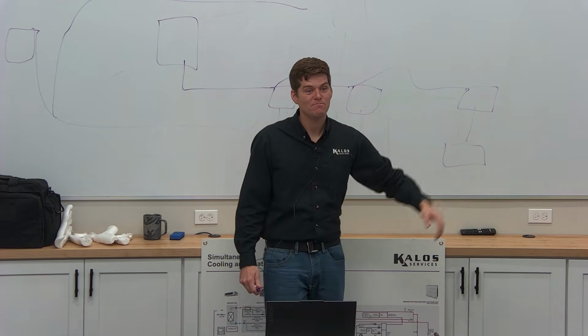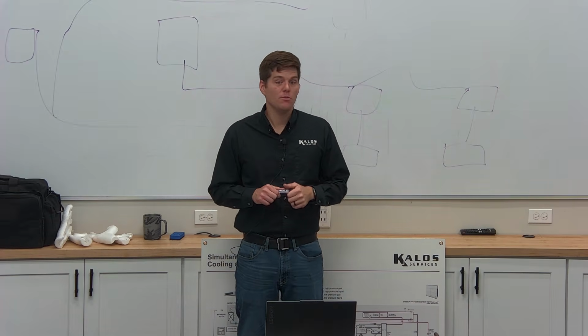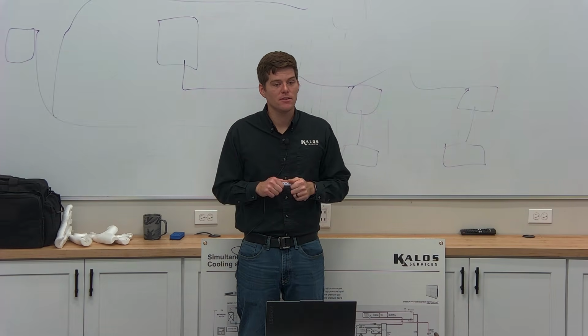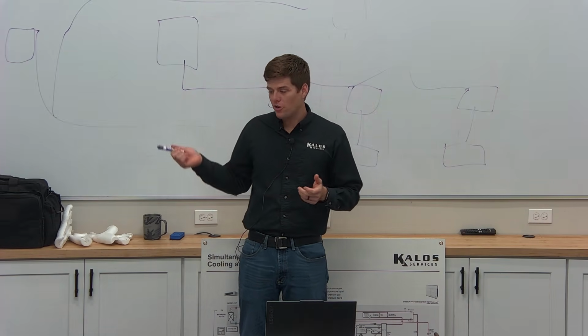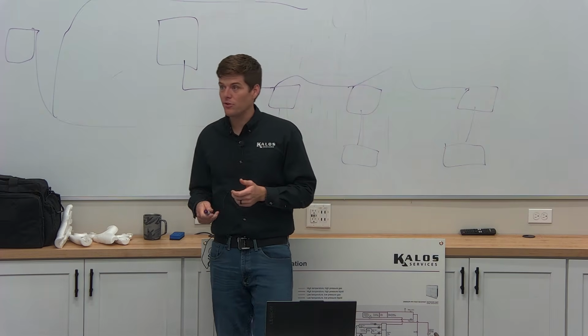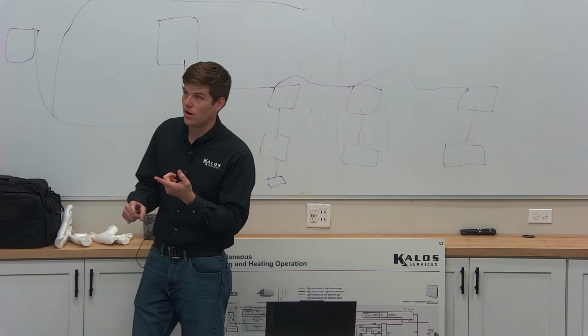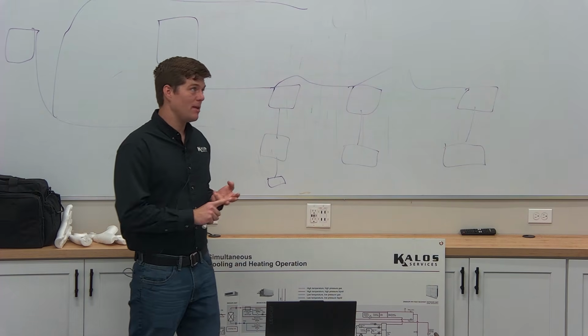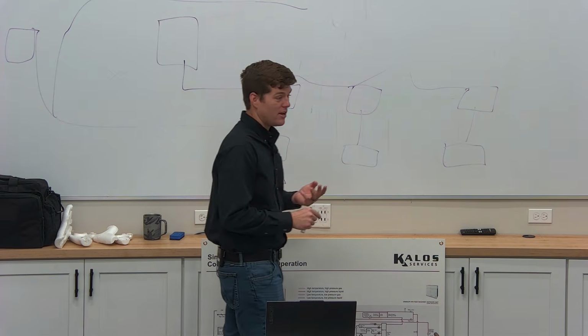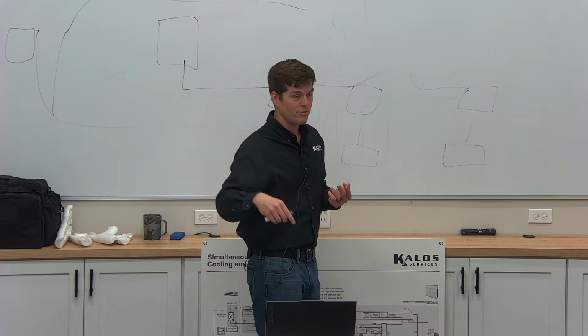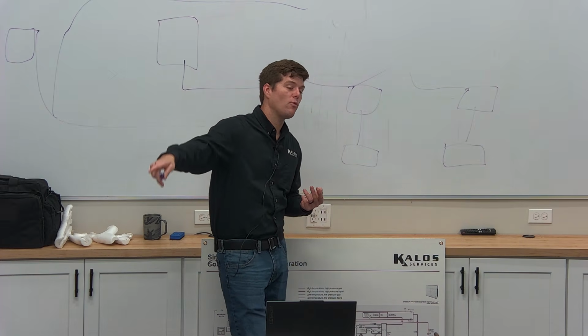So how do you program that? You don't program it. It comes programmed already. Auto addressing. You hook your indoor units to your outdoor unit. The outdoor unit knows exactly what size the indoor units are, where they're at. It gives them a name. Your name is Sally. Your name is Harry. You're 01. You're 03. You're AB3674.